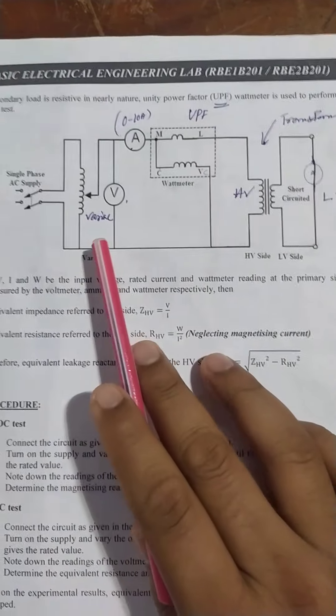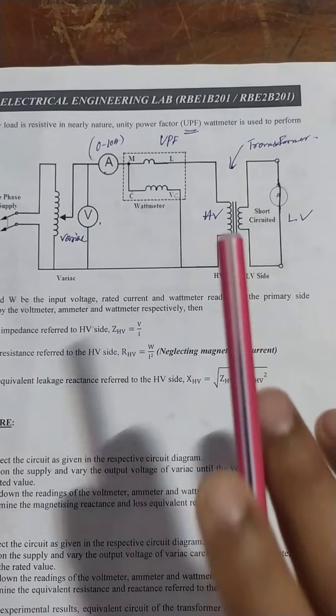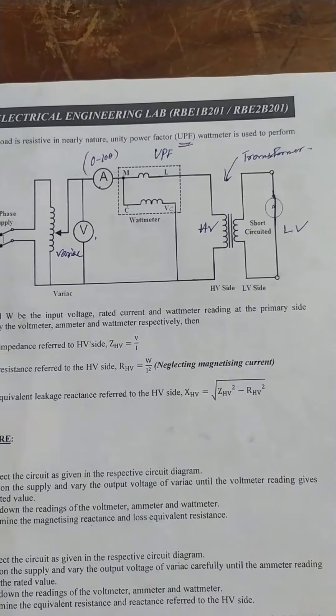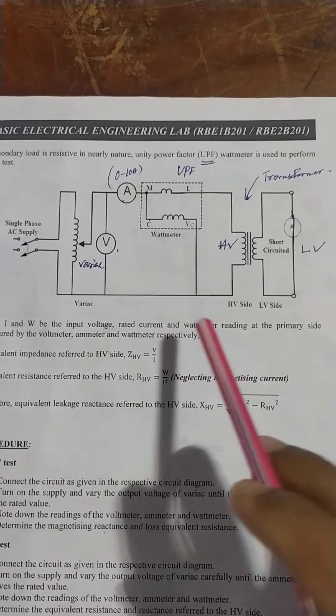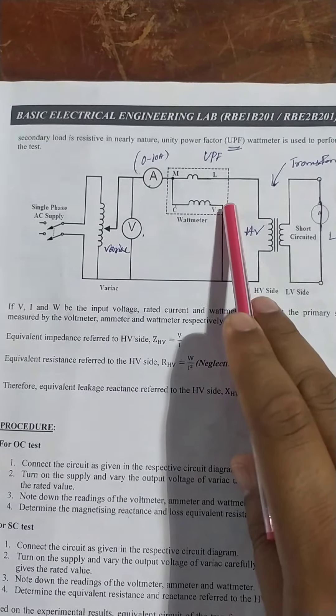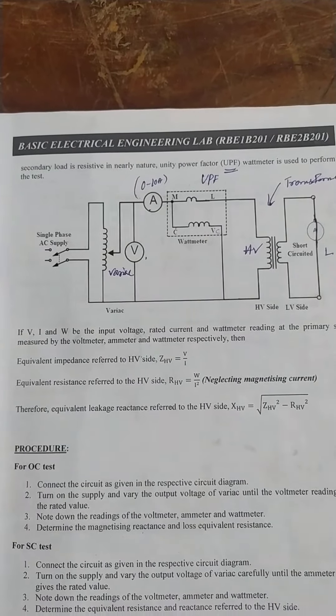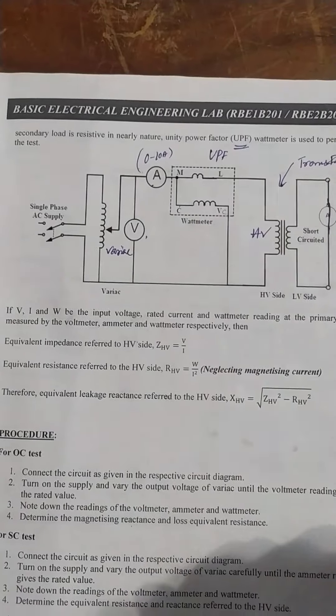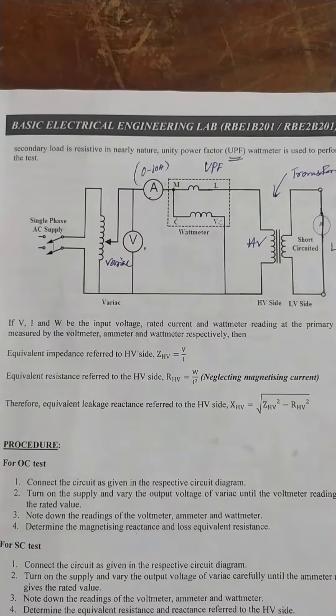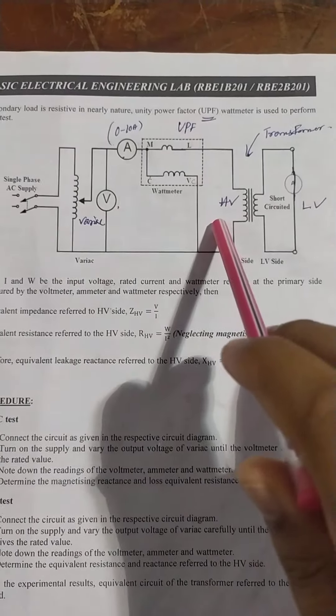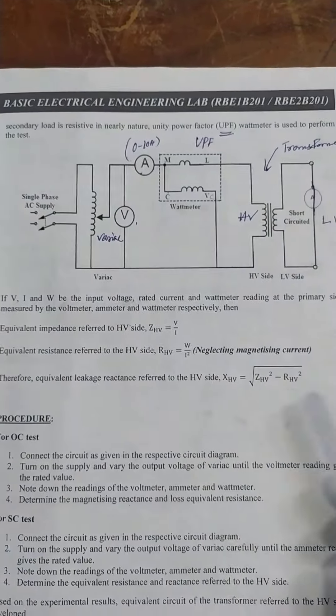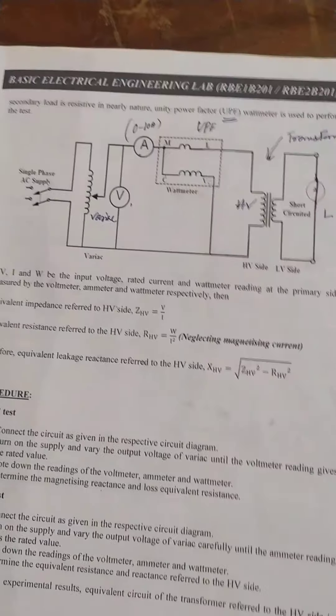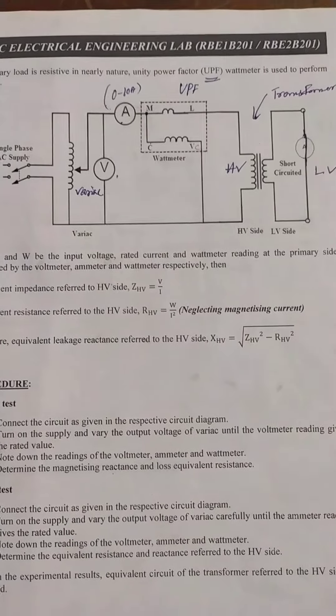We will be applying the rated current by varying the voltage slightly until we get the rated current value on the HV side. Once we reach the rated value we stop and note the voltmeter, ammeter, and wattmeter readings. From these readings we find the winding parameters — specifically the copper loss occurring in the system — and then determine the equivalent resistance and equivalent reactance of the transformer referred to the high voltage side.